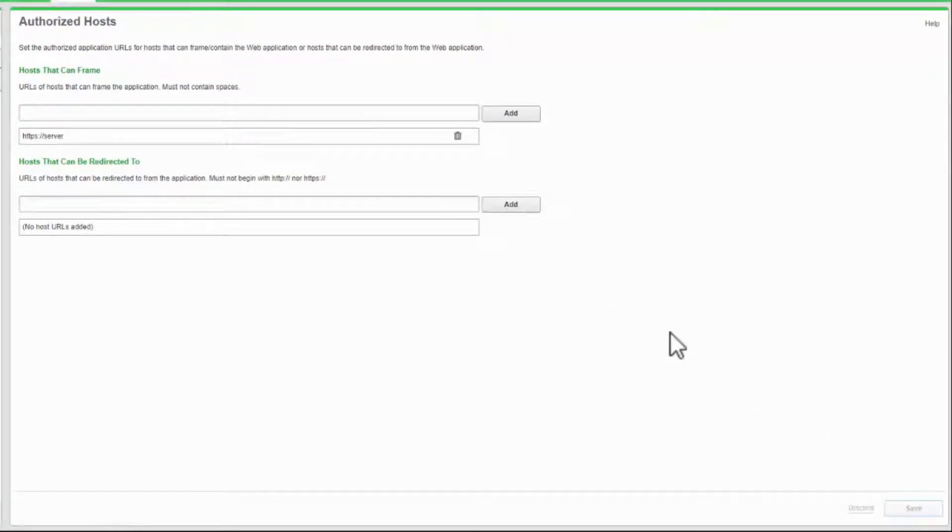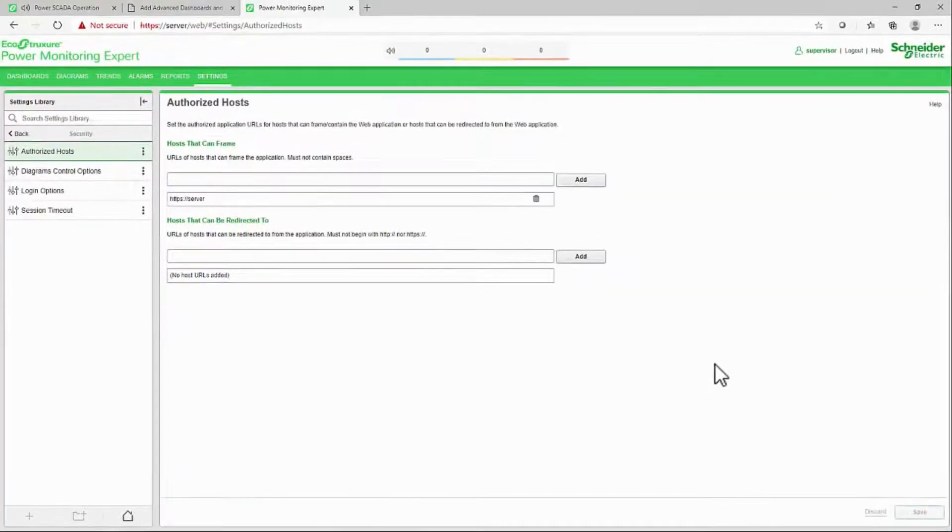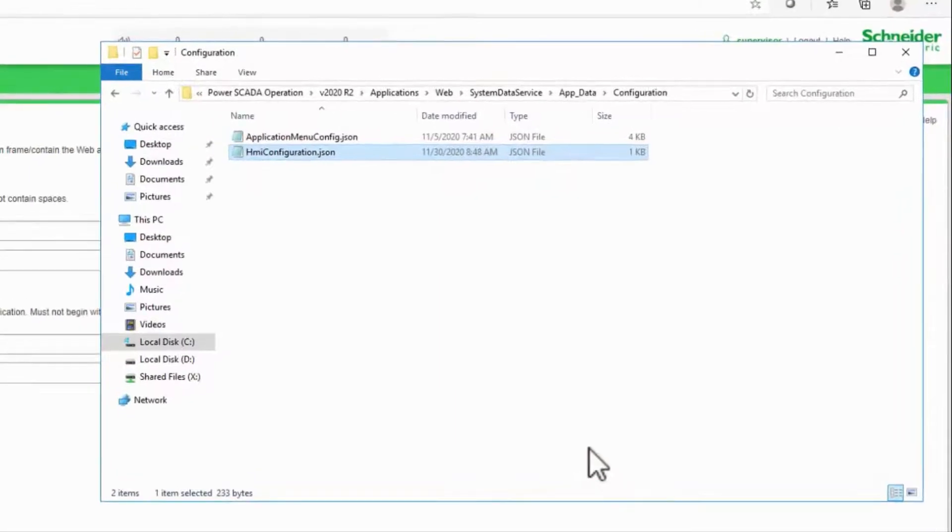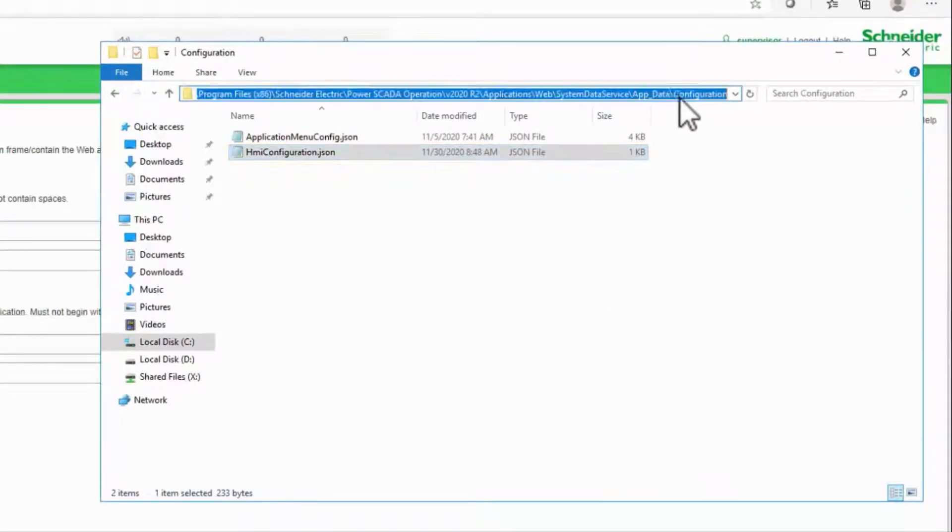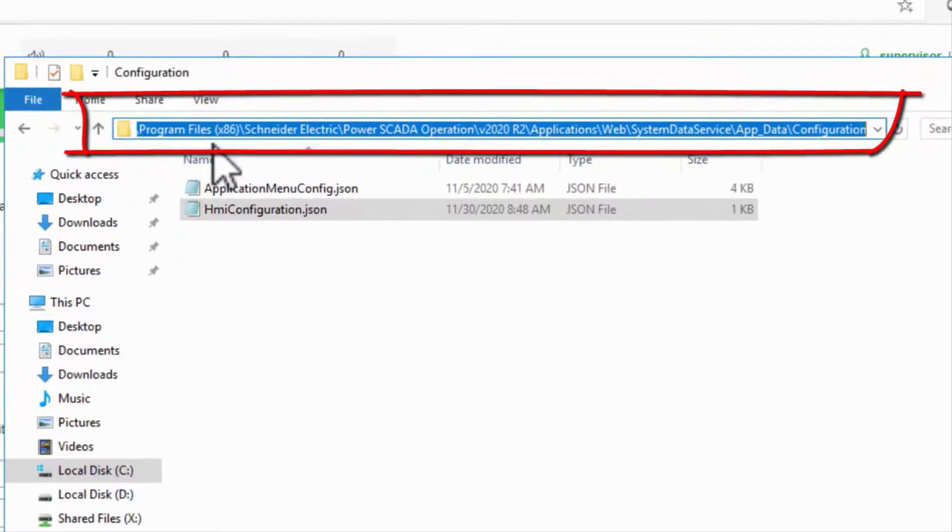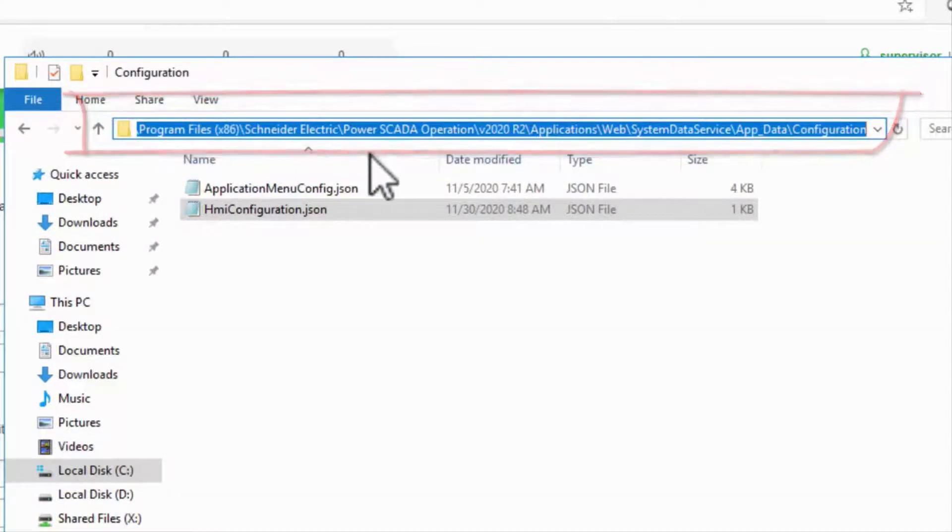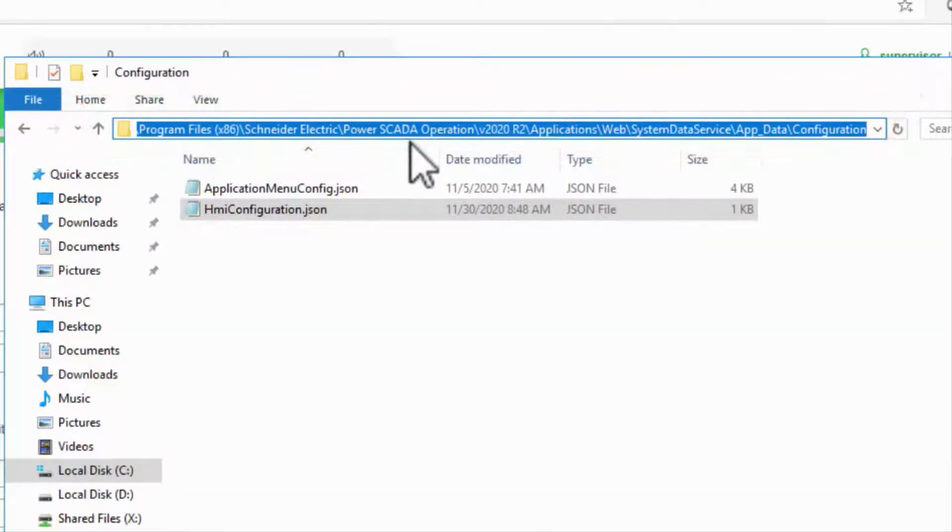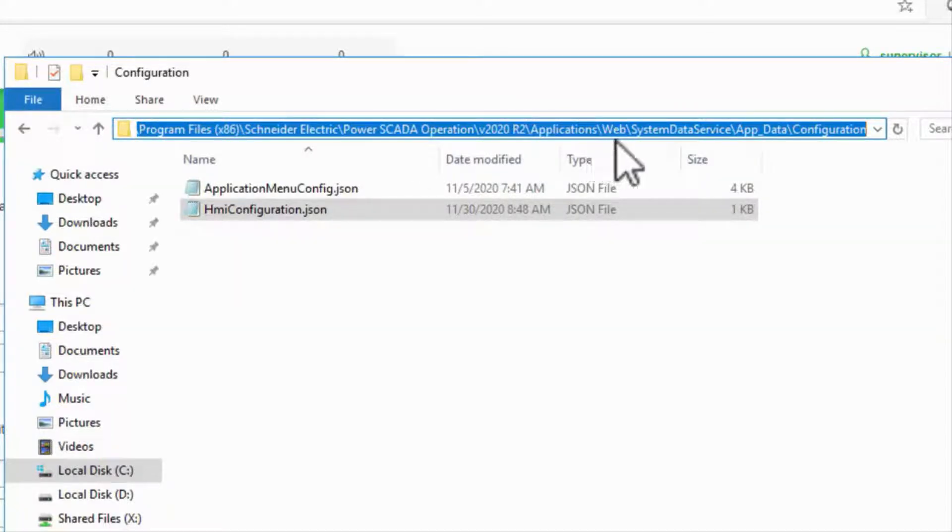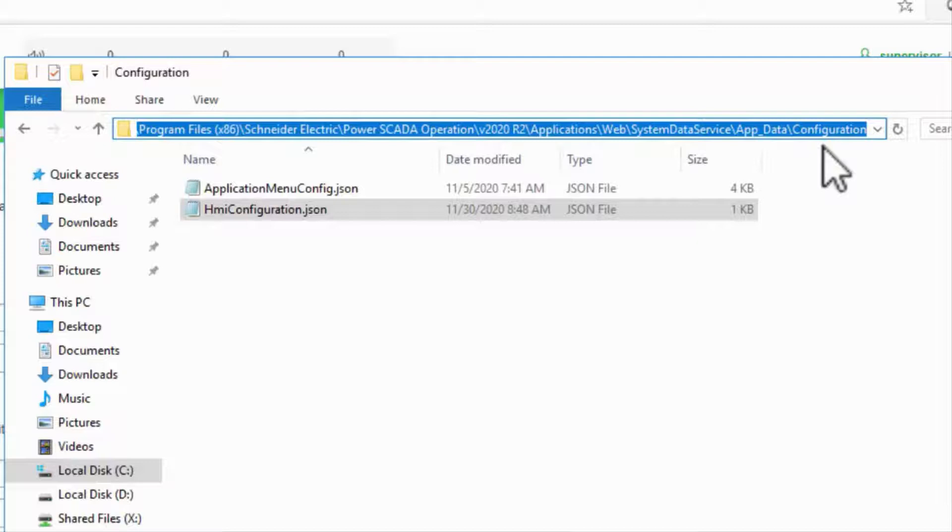Now that Advanced Reports is configured, I need to tell my web server where to find it. There are two files to configure in the folder C Drive, Program Files x86, Schneider Electric, Power SCADA Operation, the version name, Applications, Web, System Data Service, App Data, Configuration. I know that's a mouthful.